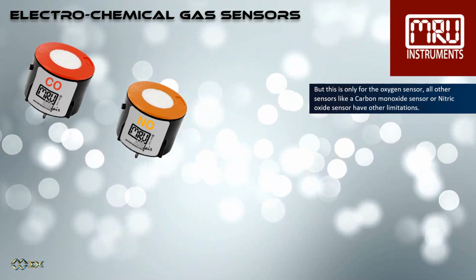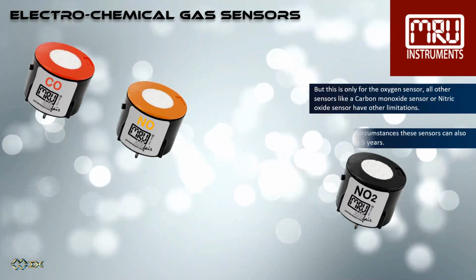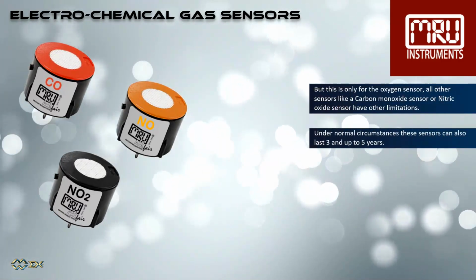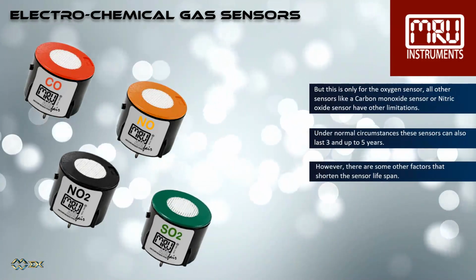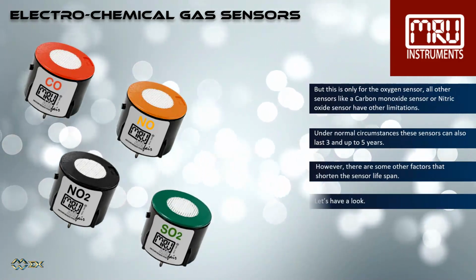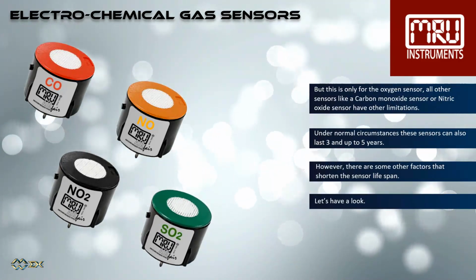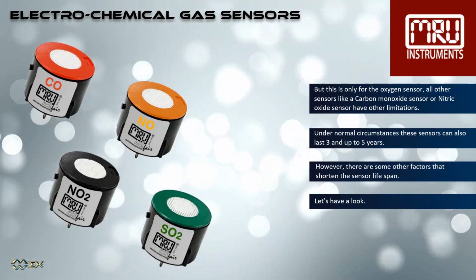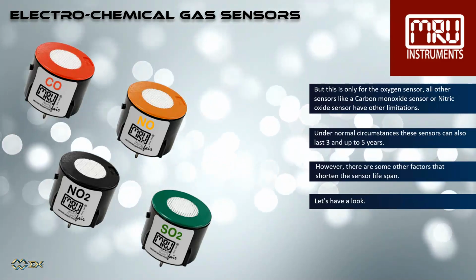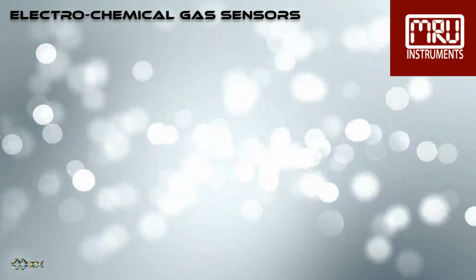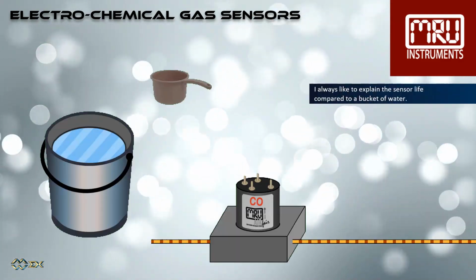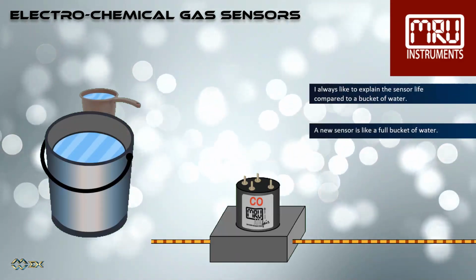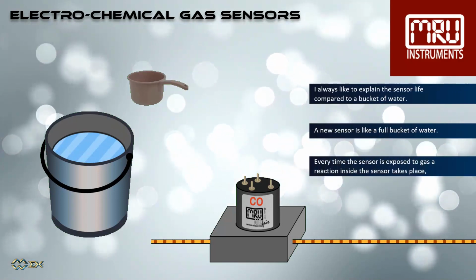All other sensors like a carbon monoxide sensor or nitric oxide sensor have other limitations. Under normal circumstances, these sensors can also last 3 and up to 5 years. However, there are some other factors that shorten the sensor lifespan. Let's have a look. I always like to explain the sensor life compared to a bucket of water. A new sensor is like a full bucket of water.